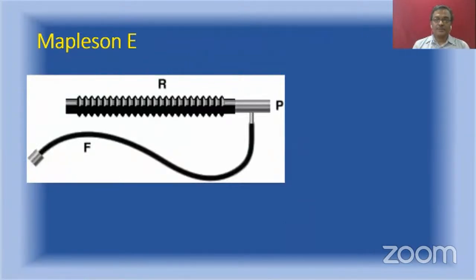And this is the modification of the T-piece. What modification you find here? In the original T-piece, there was no expiratory limb. This reservoir tube was lacking in the original T-piece, which is added in Mapleson E. And what's the function of this reservoir tube? Suppose there is no reservoir tube and suppose there is no expiratory limb. What will happen? During spontaneous breathing, the air can go into the patient's lung and can cause air dilution. So that can result in dilution of the anesthetic gases. So to prevent that air dilution, an expiratory limb is added. And there is one classification also for T-pieces: without any expiratory limb, with an expiratory limb whose volume is less than tidal volume, and the third one is with an expiratory limb whose volume is greater than the tidal volume. This is called Harrison's classification.